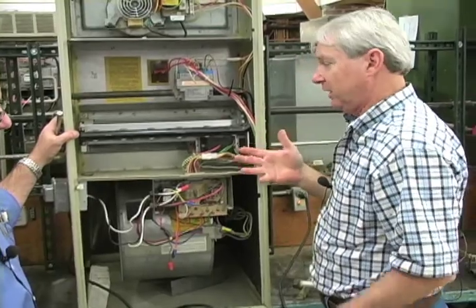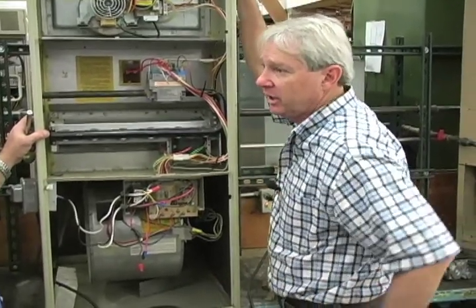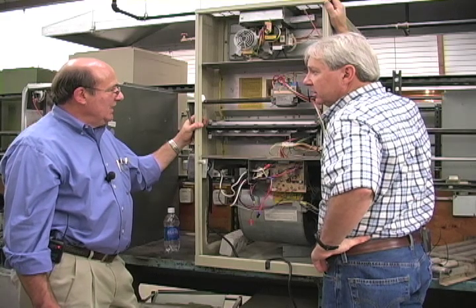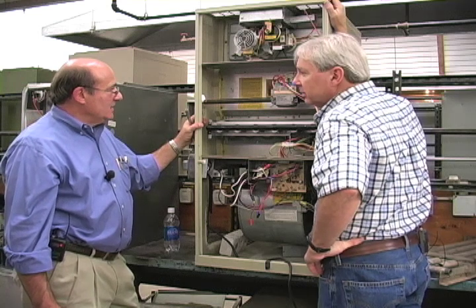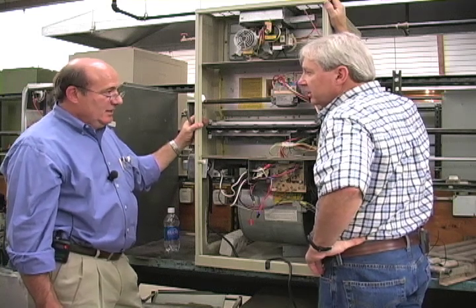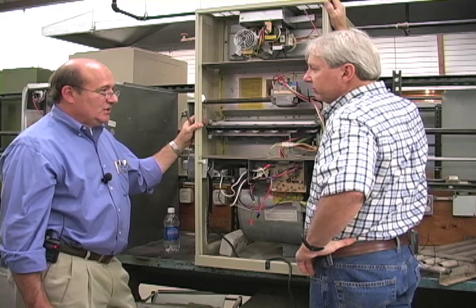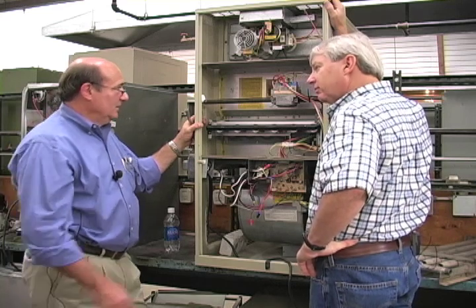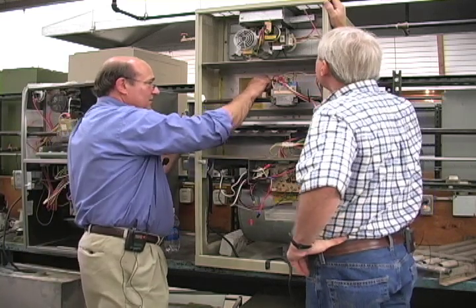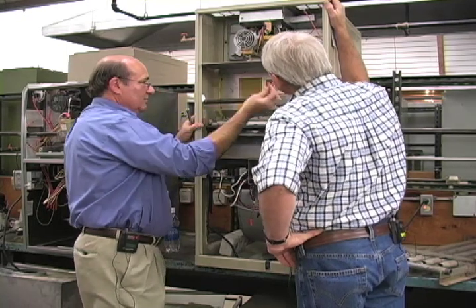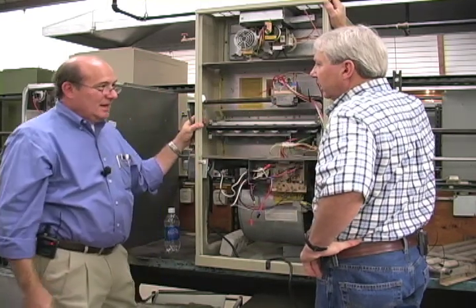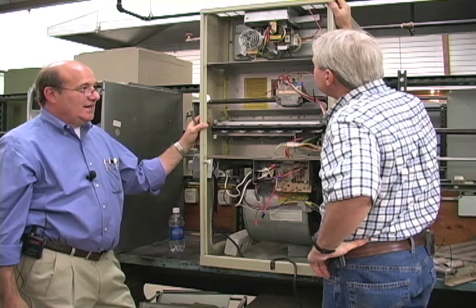More, it'll be a failure of the system to respond to the call for heat. Yeah, pretty much. Now, the one thing that's kind of nice about these systems, though, is that you can simulate a limit switch, a limit failure on the system. You can just take one of these wires here, pull it right off. At that point, you should see those main burners go right down.